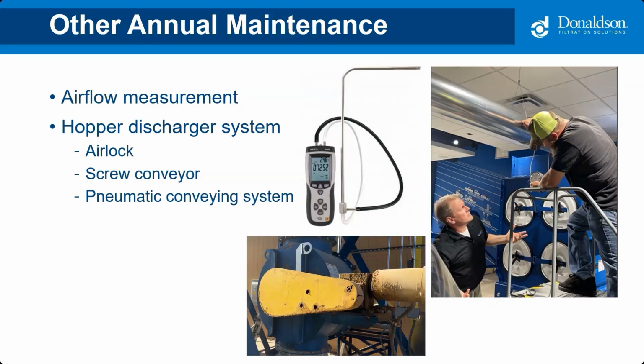Like I mentioned before, of adding or removing a drop, that's where you go deeper into a question like that. Did somebody add a drop that wasn't here before, or take one away? Is the damper not adjusted properly? It's just a nice gut check to make sure your system is still running as designed, right? Again, going back to get the most out of it, you've got to make sure that thing is still running at design flow.